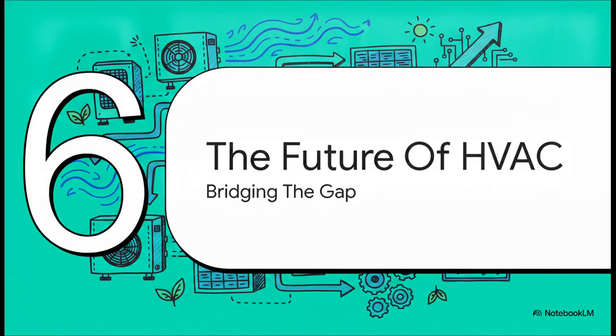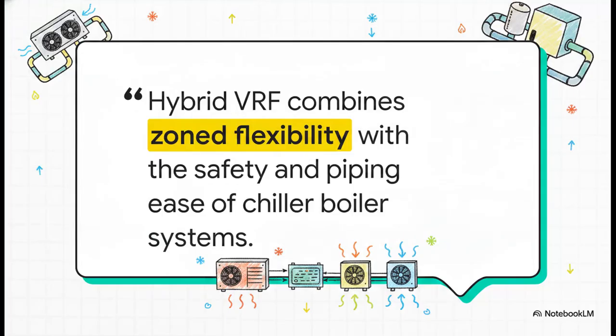Let's take a step back and look at the big picture in Section 6, the future of HVAC. This quote really hits the nail on the head. Think about it. For decades, we've treated VRF systems and traditional chiller boiler systems as two totally separate design philosophies. Hybrid VRF bridges that gap. It gives you the incredible energy efficiency and the luxury of simultaneous heating and cooling, all while making the indoor installation so much easier and completely risk-free when it comes to refrigerants for the folks actually living or working inside.